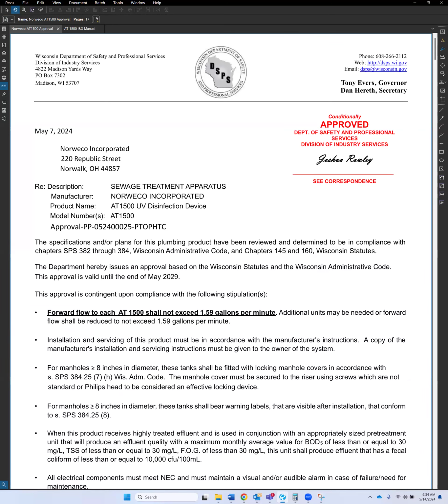Thank you. Does the 6-month maintenance interval require anything besides cleaning of the lamp and making sure that it's still functional, or what else is required at that 6-month interval? The 6-month intervals are going to be to disassemble and clean it, and then reinstall it. That way you're just ensuring that the device is clean and you're getting the transmittance of the UV that you need to kill the fecal and other bacteria and pathogens.